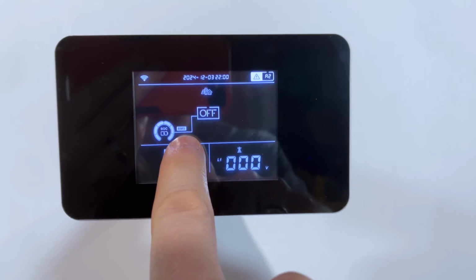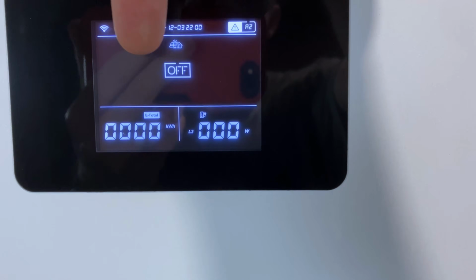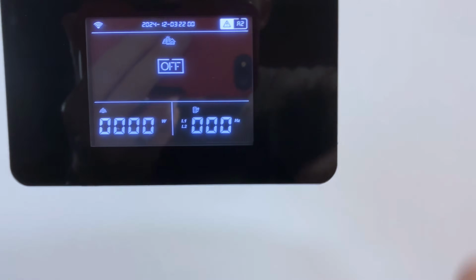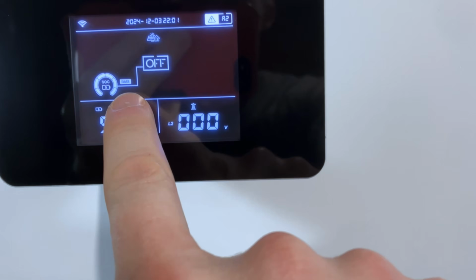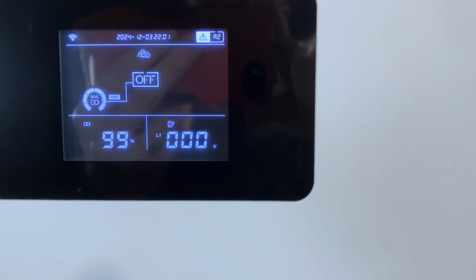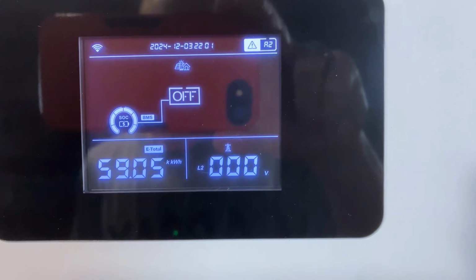BMS is at 99%, and this icon signifies there's BMS communications. If we look at inverter 2, we can see it now has the solar panel with the house icon, which signifies it's in self-consumption mode. It's still blinking, but apparently it's going to do that. The BMS icon signifies we have communication, and when it rolls around, you'll see this is at 99% state of charge as well. Both inverters currently have the R2 error message, regarding missing grid power.